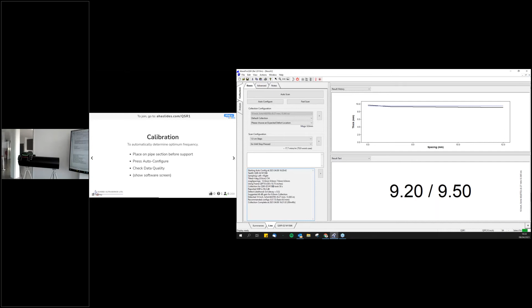Okay. The signal to noise ratio is high, it's close to 60 dB. That's great. Also notice that the equipment automatically detects the frame size, so you don't have to worry about that. So no form of manual input is required. And what else to highlight? Yes, on the bottom right here, we can see two numbers showing the top and bottom path thicknesses. These are the thicknesses that the QSR1 has measured at this point. All right, so that's done for calibration. Nice and simple. Just hit the button and make sure that the status is good.